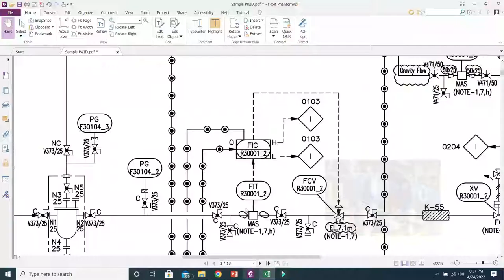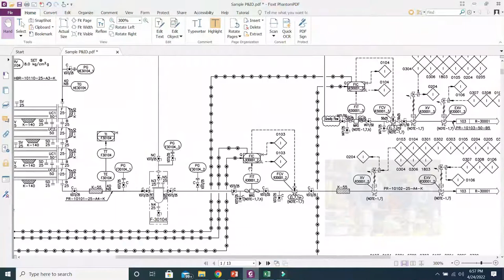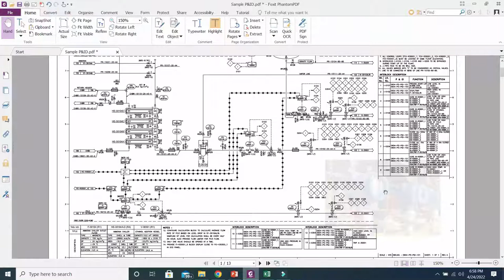Then P&ID number. Although we are referring to a P&ID, there will be a particular number for each P&ID. In a project there can be lots of PNIDs, like 200 or 300 PNIDs. We will use them one by one, and each P&ID has a particular number. On whichever P&ID we work for each and every instrument, we will define that P&ID number. Generally the P&ID number is mentioned at the right bottom side, in the title block, which is blank here, but you can see at the bottom there is a P&ID number or drawing number. This is 0904-PS-PID-101. So this is the P&ID number.